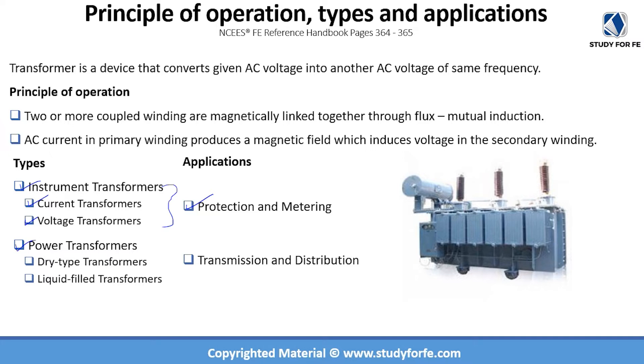Then we have power transformers, which are further classified as dry type transformers or liquid or oil-filled transformers, and these are primarily used for transmission and distribution. The big transformers you see in substations are power transformers, but the small CTs and VTs which you find inside switchgear or MCCs belong to the instrument transformer category.